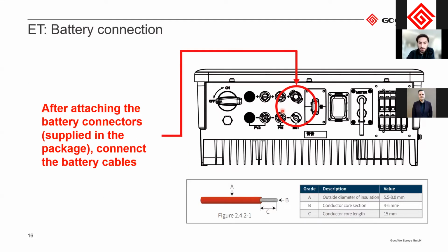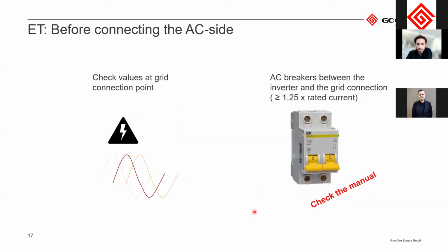After attaching the PV inputs, then you should attach the batteries. And they are also here next to the MPPTs, and it's quite easy to find. It says BAT on that. And here also use the connectors that are supplied in the package. And also here, when you use the cables, please always observe the cable sizes.